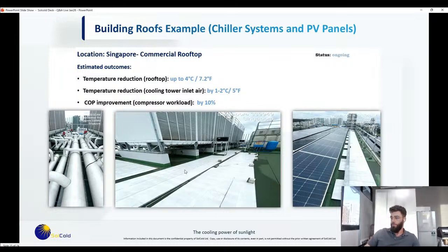What we did, with CapitaLand, is put our SolCold material around their chiller system. When we put our SolCold material around the chiller system, the air intake being sucked into their chiller systems is up to 4 degrees Celsius cooler. Because it's cooler, the system has to work less hard to cool that air.